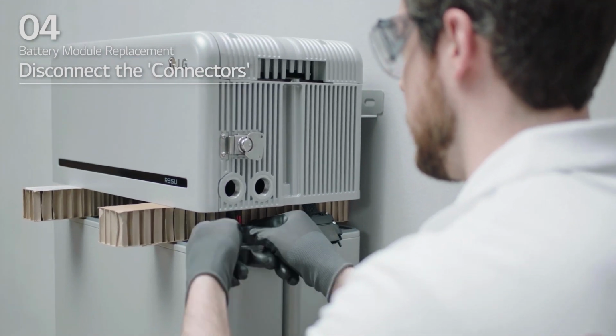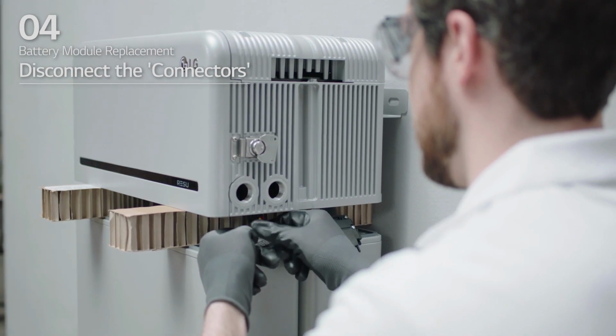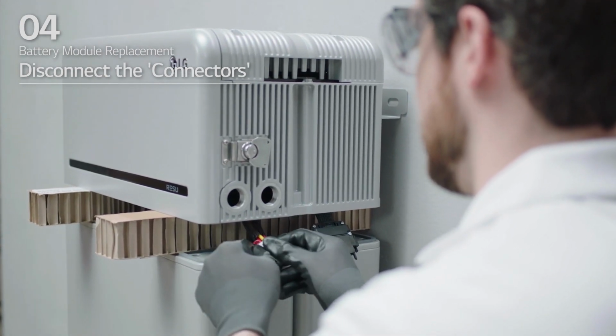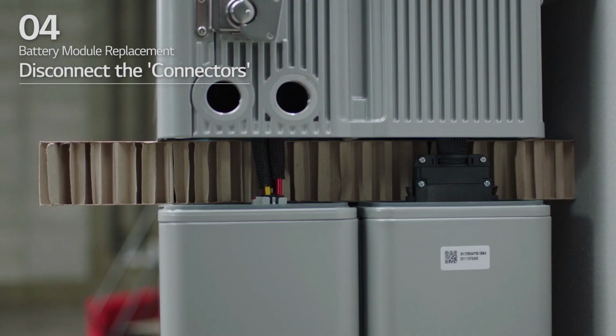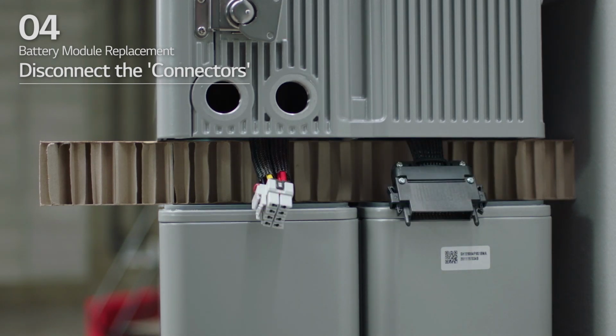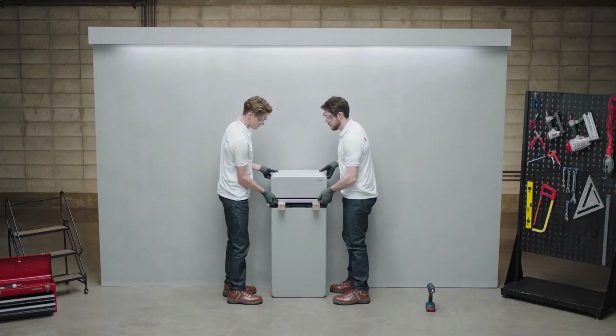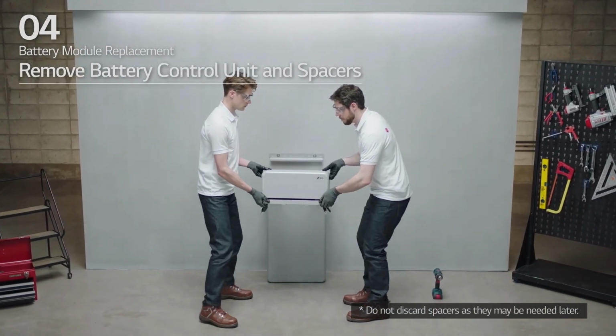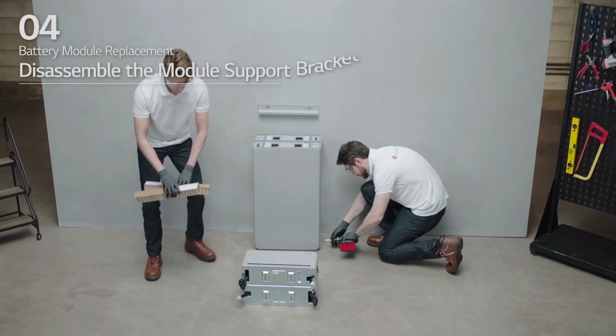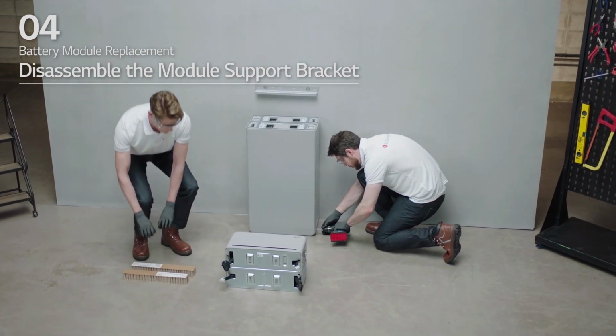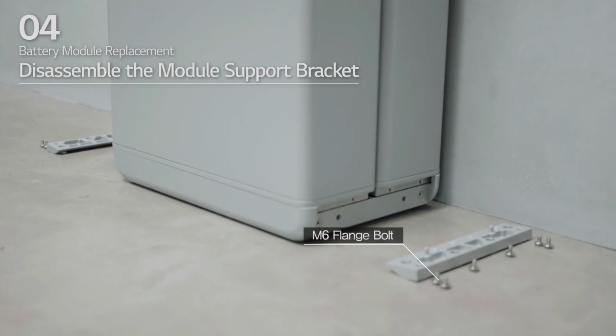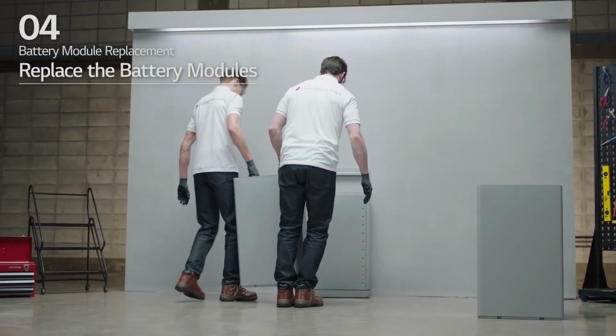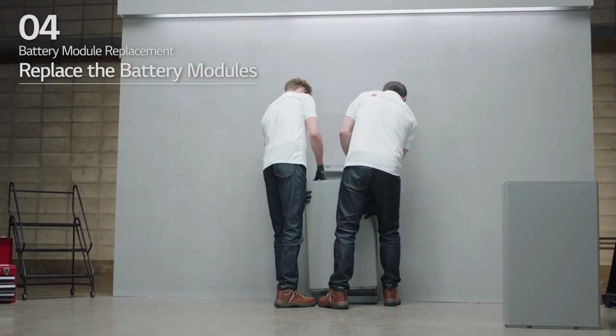To remove the sensor connector, push in the sides of the connector and pull out the connector vertically. Then, pull the connector out to the side of the battery module. Then remove the battery control unit and spacers. Disassemble the module support brackets with 6 M6 flange bolts on each side. Replace the disabled battery modules with the new battery modules.